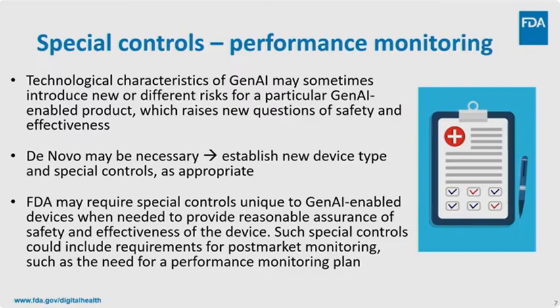Which raises, in turn, new questions of safety and effectiveness. So what that means is that a de novo may be necessary to regulate that product. And through that de novo process, the output is that FDA would then establish a new device type, new regulation, and that would be accompanied by special controls as appropriate for that new device type. So FDA may require special controls that are unique to generative AI-enabled devices when needed to provide that reasonable assurance of safety and effectiveness of the device.